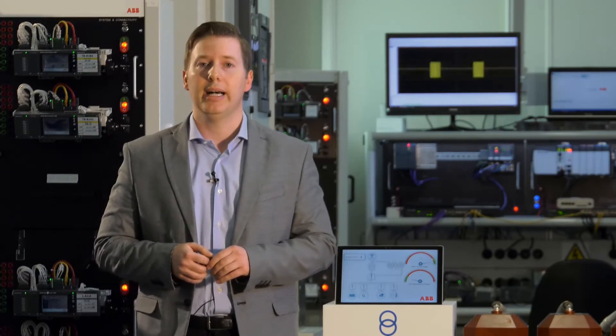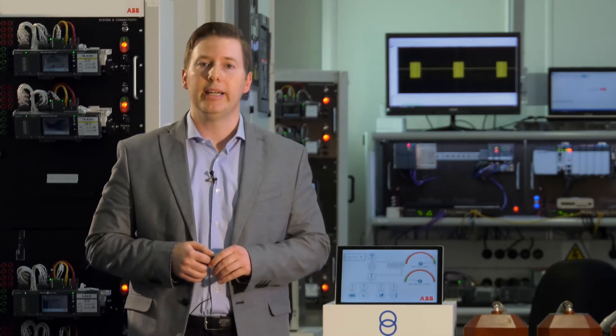Usually such a disconnection is carried out by an interface device which trips after receiving an opening command delivered by an external interface protection system. ABB has been able to develop an integrated solution in which we have embedded both the function of interface device and interface protection system.